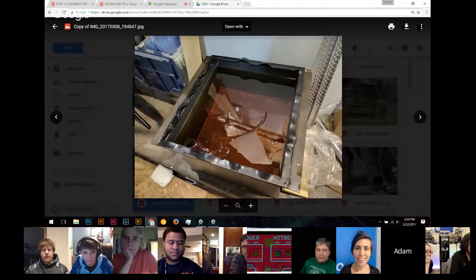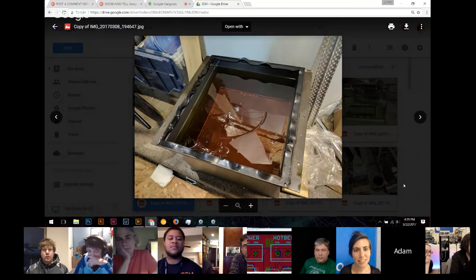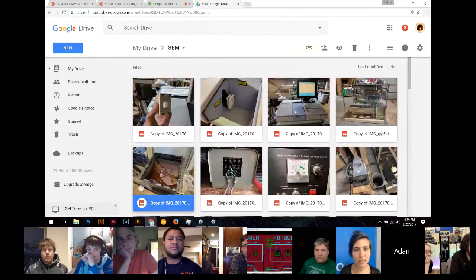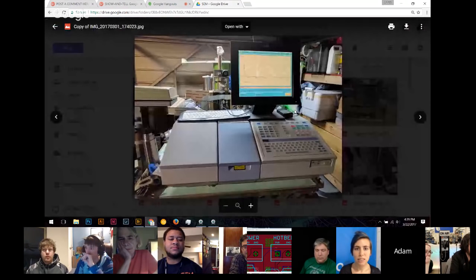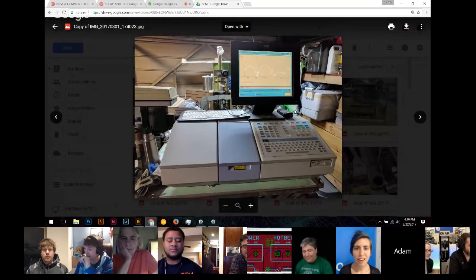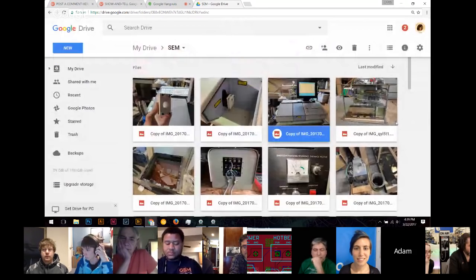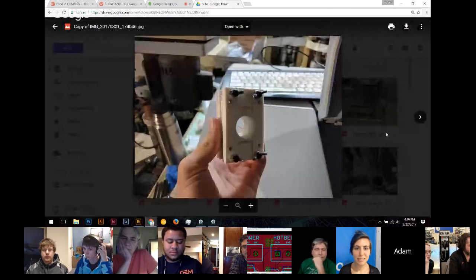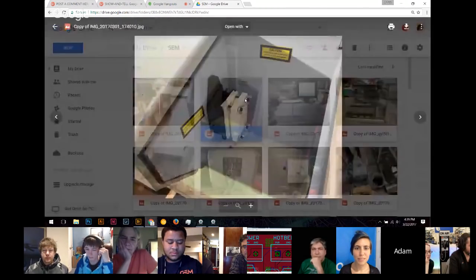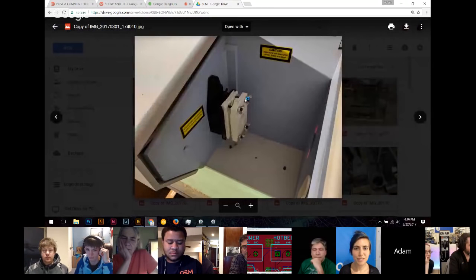Now, this oil kind of scared me at first because I thought, oh, PCBs are bad. I enjoy being healthy, so I didn't want to touch this thing until I knew for certain. So I got out an old piece of equipment I got at surplus, called a Fourier transform infrared spectrometer. I picked this thing up for $35 from a surplus store in Seattle and refurbished it. I was actually able to use a 3D printed jig I built to suspend the oil in the machine's beamline to make sure I wasn't dealing with any PCBs. Once I had that confirmed, I opened the thing up and started servicing it.